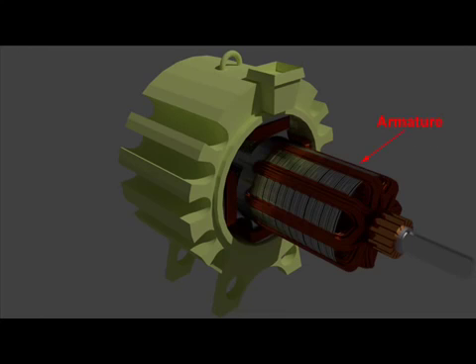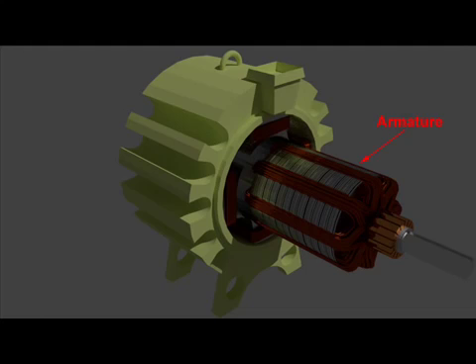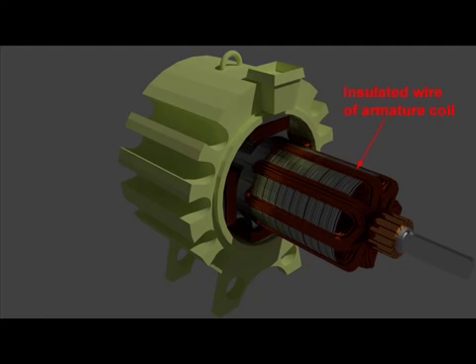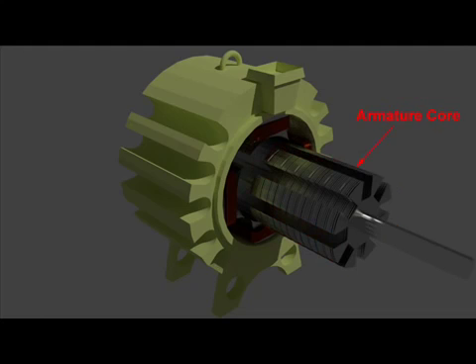Now, let us discuss the construction of the armature. The purpose of the armature is to rotate the conductors in the uniform magnetic field. It consists of coils of insulated wires wound around an iron and so arranged that electric currents are induced in these wires when the armature is rotated in a magnetic field. In addition to providing support to the armature coils, it also provides low reluctance path to the magnetic flux.